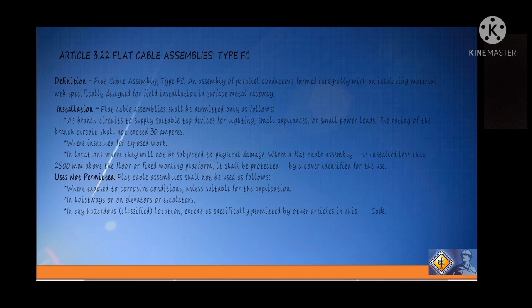So flat cable assemblies, an assembly of parallel conductors formed integrally with the insulating material web, specifically designed for field installation in surface metal raceway. So in terms of installation, as a branch circuit to supply suitable tap device for lighting, small appliances, or small power loads, the rating of the branch circuit shall not exceed 30 amperes. And also installed for exposed work.